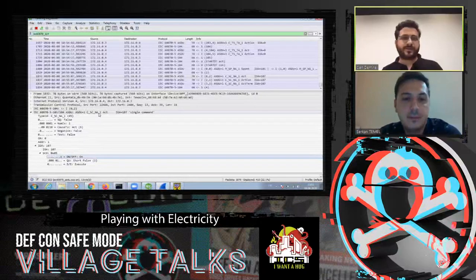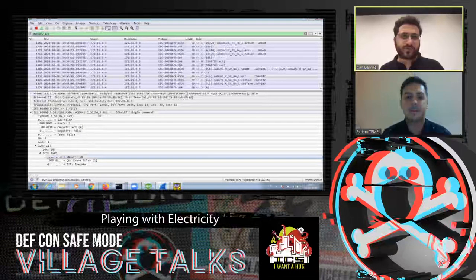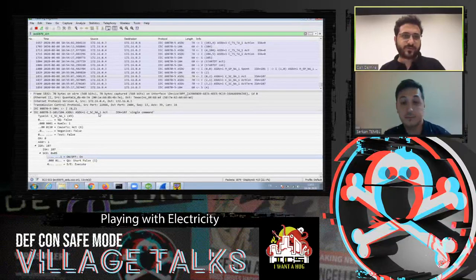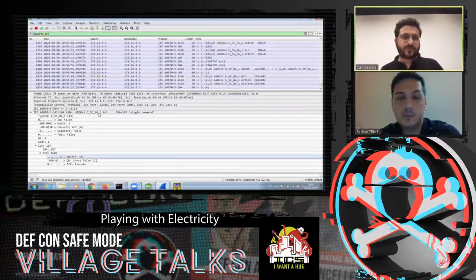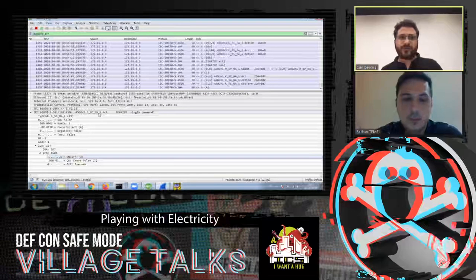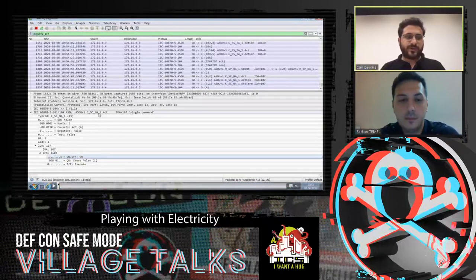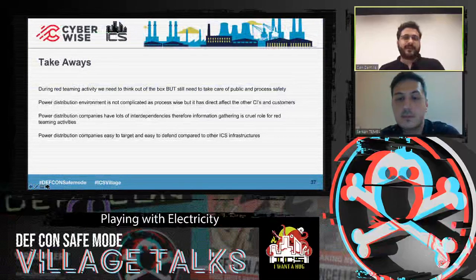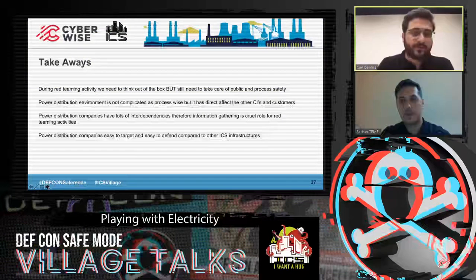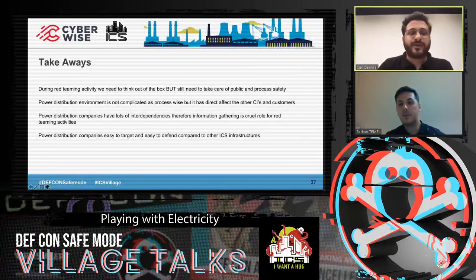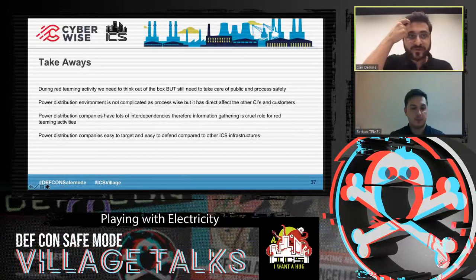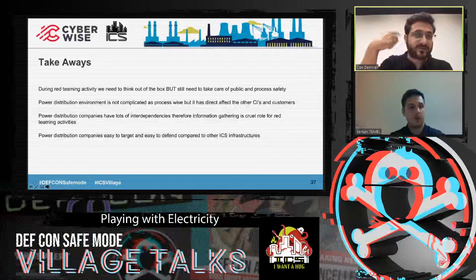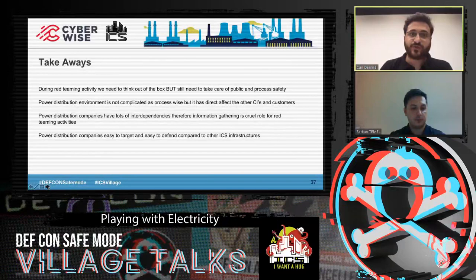Once you get into the substation, you pull data through the protocol, and you send commands through the protocol again. In that case, single commands or double commands are supported by 104, and then you are able to shut down the electricity. If that's your end goal, you may apply very different types of scenarios and red teaming activities, but we want to show you that it can be done. There are some safety mechanisms or configuration mechanisms to avoid it. Sometimes you implement an IP-based solution or an anomaly detection solution to counter that kind of activity.